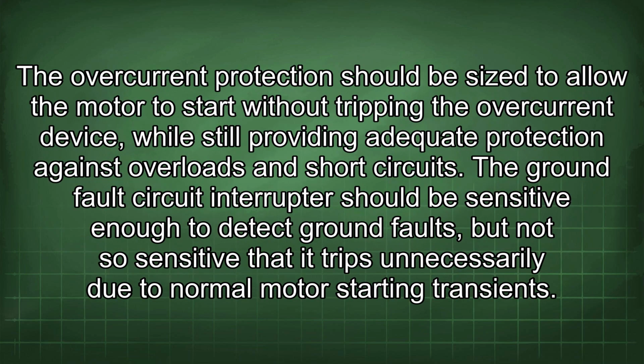The overcurrent protection should be sized to allow the motor to start without tripping the overcurrent device, while still providing adequate protection against overloads and short circuits. The ground fault circuit interrupter should be sensitive enough to detect ground faults, but not so sensitive that it trips unnecessarily due to normal motor starting transient.